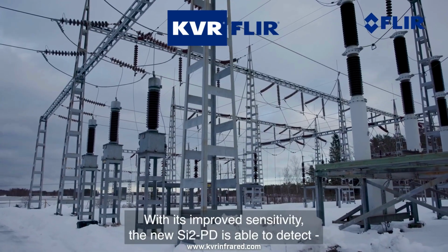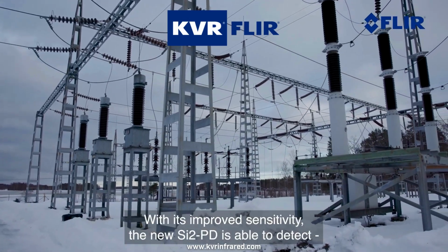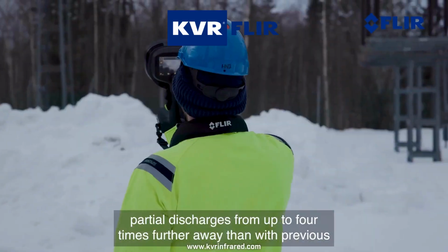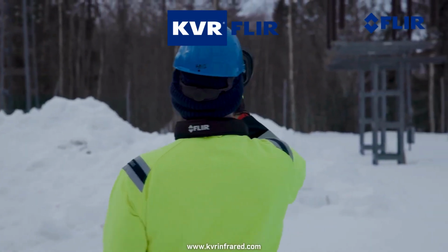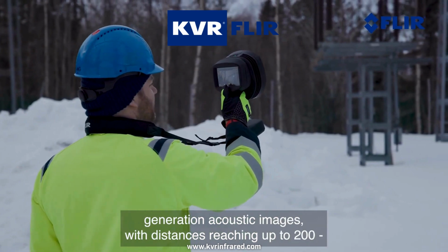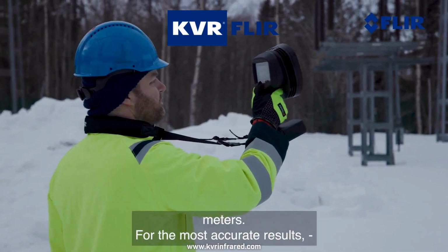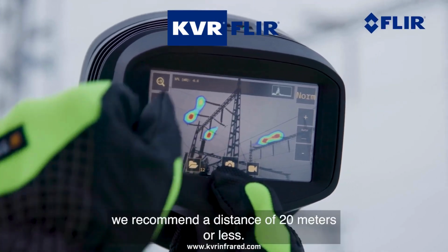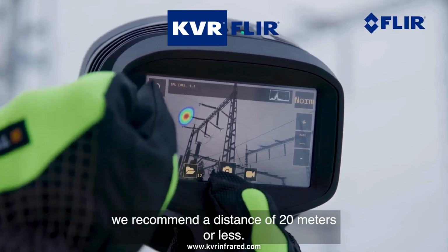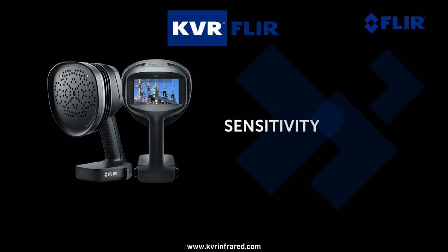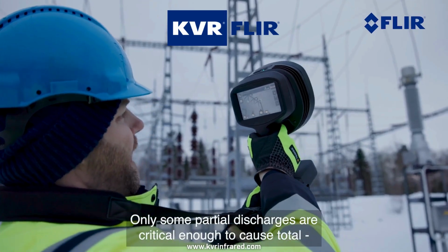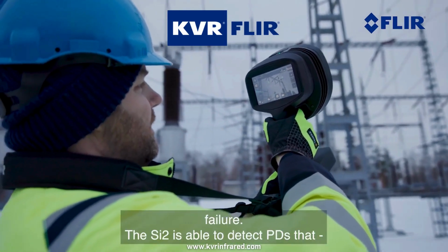With its improved sensitivity, the new Si2 PD is able to detect partial discharges from up to 4 times further away than with previous generation acoustic imagers, with distances reaching up to 200 meters. For the most accurate results, we recommend a distance of 20 meters or less. Only some partial discharges are critical enough to cause total failure.